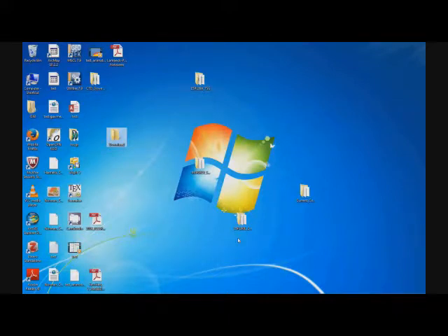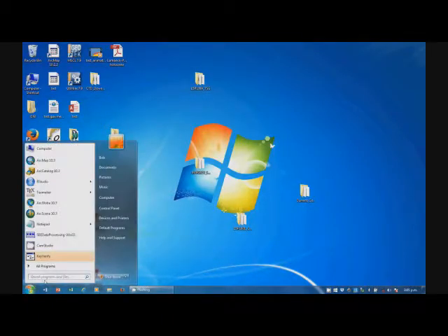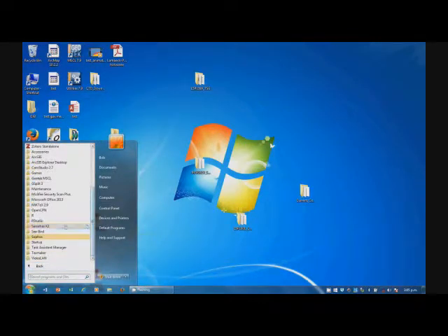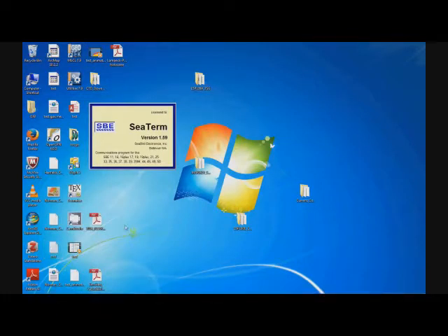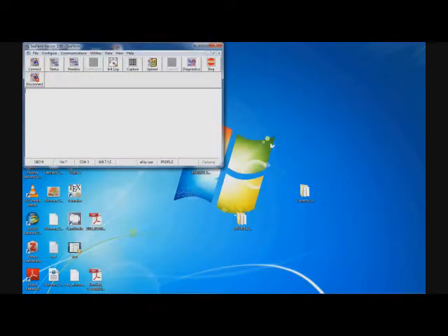See the software. This one today is called SeaTerm, and this is the software we use to download data from the CTD onto the computer. So the first thing we'll do is set up the software. The software will be on your computer under Seabird and SeaTerm. Prior to connecting to the CTD, you need to make sure that the software is configured properly to talk to the CTD you are currently working with.